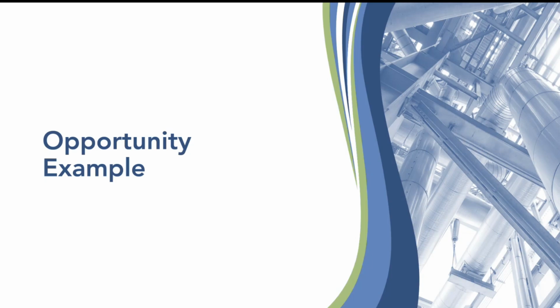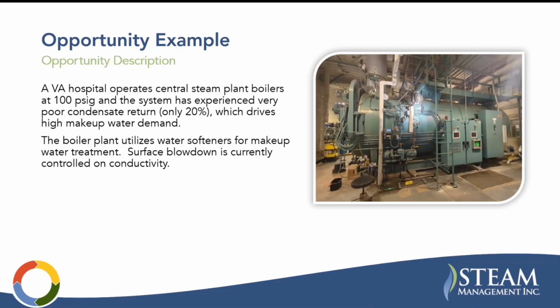Okay, so on to an opportunity example. This is a VA hospital operating central steam plant boilers at 100 pounds. The system has experienced very poor condensate return, which drives high makeup water demand. The boiler plant utilizes water softeners for makeup water treatment. Surface blowdown is currently controlled on conductivity.